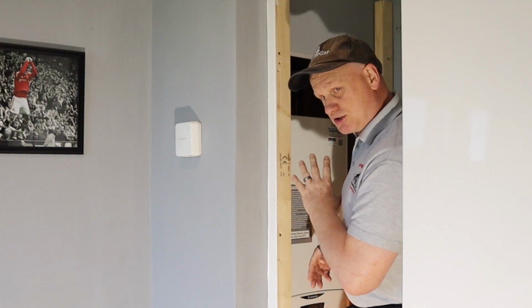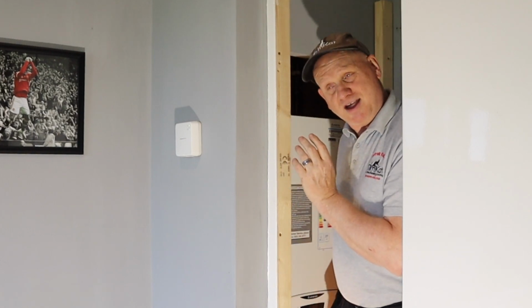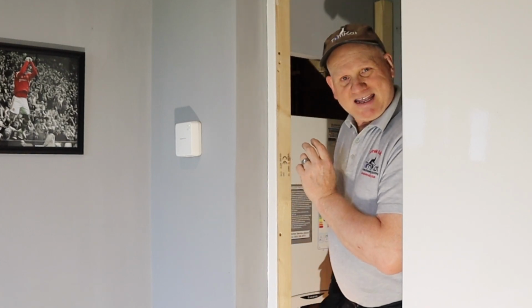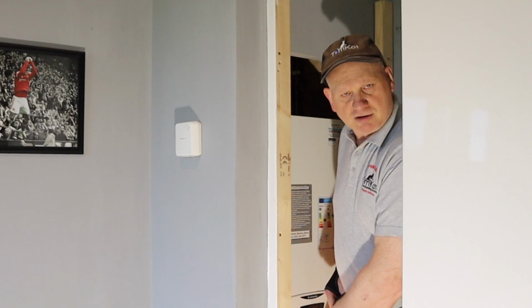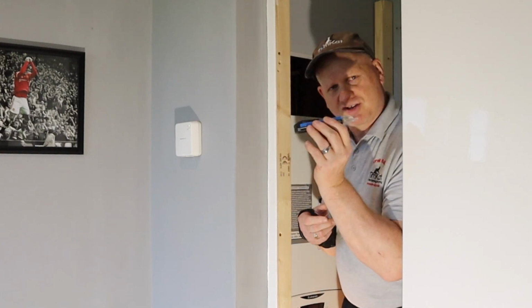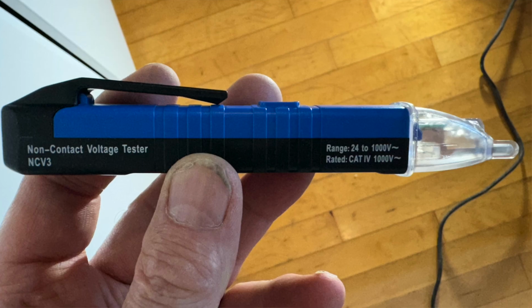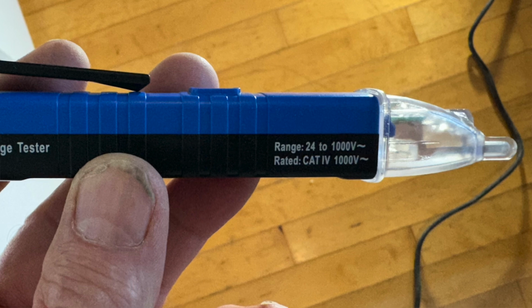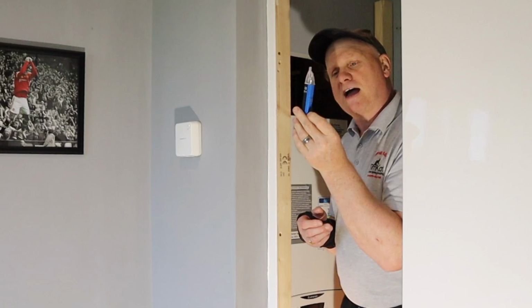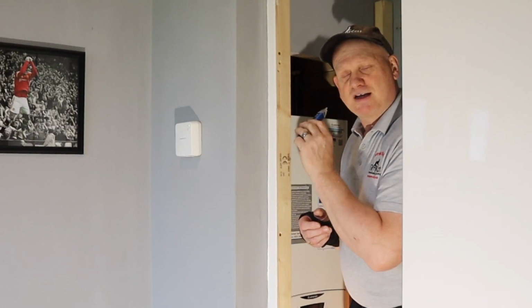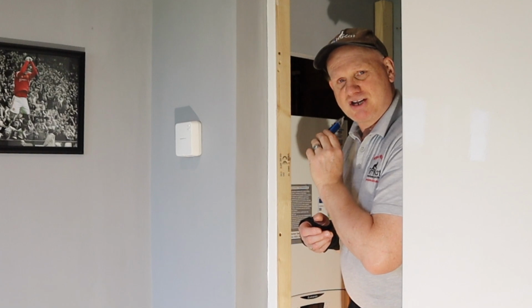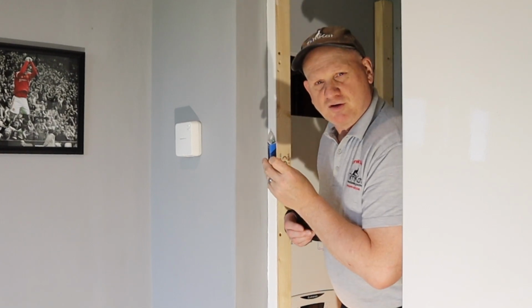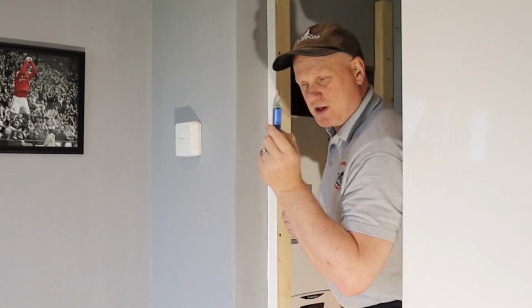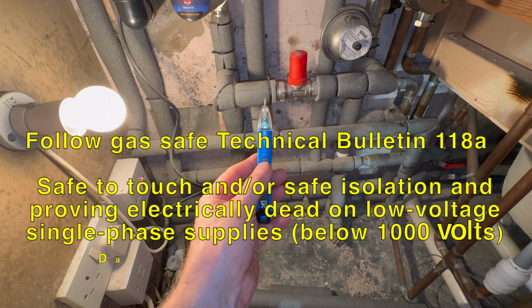Anyway, before I touch the boiler, first thing I need to do is get out my little non-contact voltage detector or indicator, which is a 24 volt to 1000 volts, and see if it's safe for me to actually touch this boiler before I service it. So let's get on with that. Now you should know the drill by now.